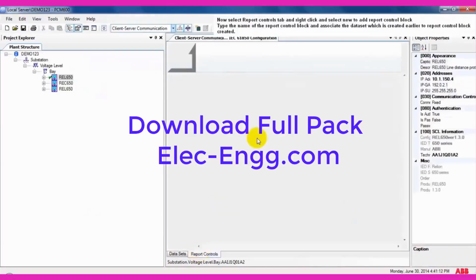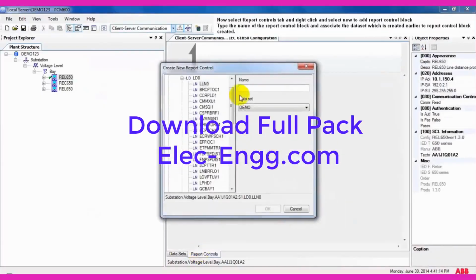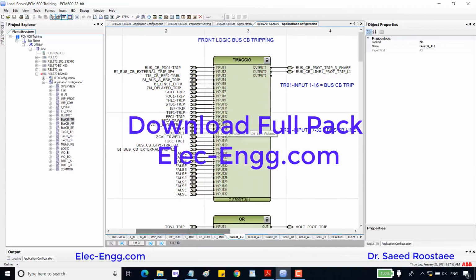Now select the report controls tab and right-click and select New to add the signals. The signals connected to input numbers 1 to 16 can initiate the 3-phase trip, and inputs 17 to 32 can initiate single-phase tripping for the phase 1 or phase L1.